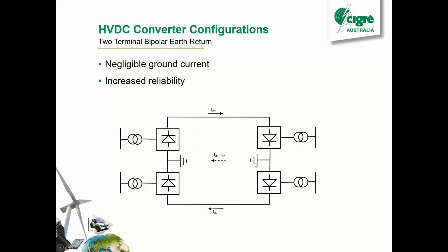Yeah, the other option is to have a metallic return here, so you run another cable between your stations. So that has to be the same thickness, right? Because it's carrying the same current, so it can still be quite expensive, but you can save on the insulation. You don't need nearly as much insulation because you're only going to be dealing with 1,000 or 2,000 volts sort of thing.